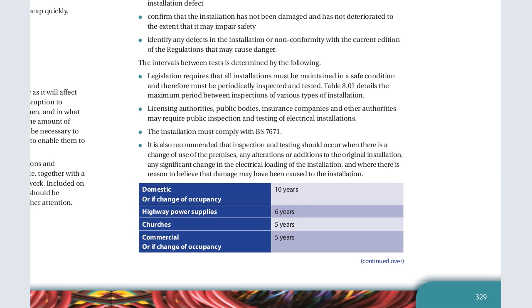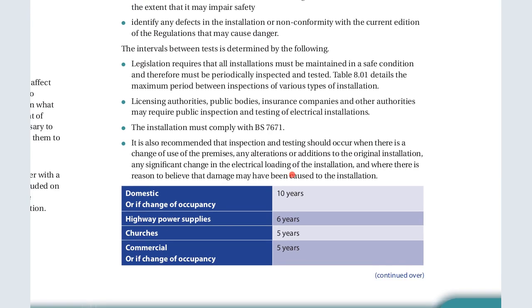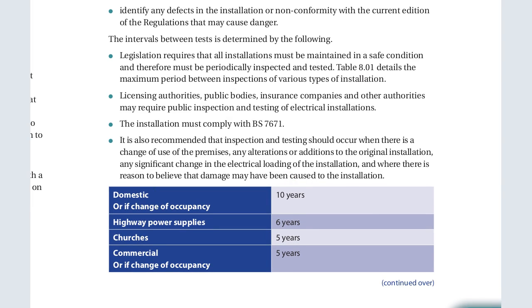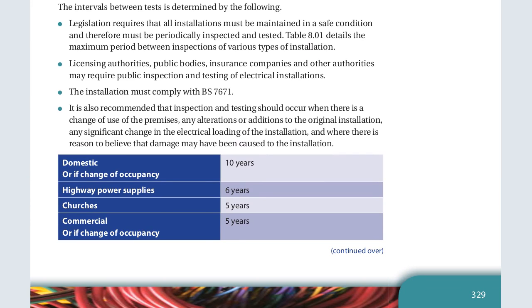Licensing authorities, insurance companies, and other authorities may require periodic inspection and testing of the electrical installation. The installation must comply with the standard, that is BS 7671. So you can now see the duration of inspection. It is also recommended that inspection and testing should occur when there is a change of use of premises, that is any alteration or addition to the original installation, any significant change in the electrical loading of the installation, and where there is reason to believe that damage may have been caused to the installation.